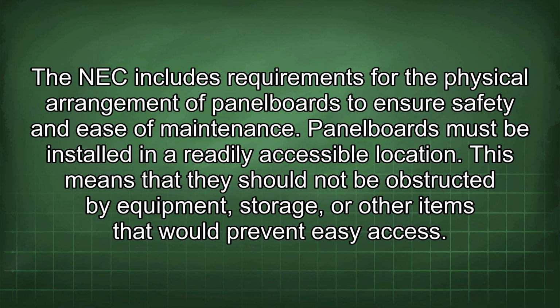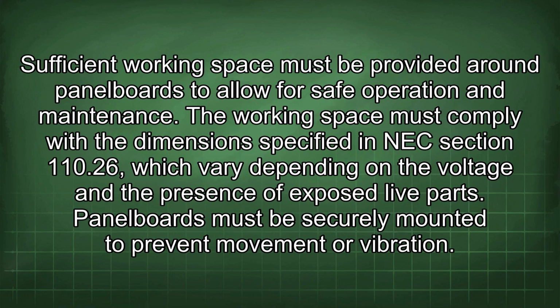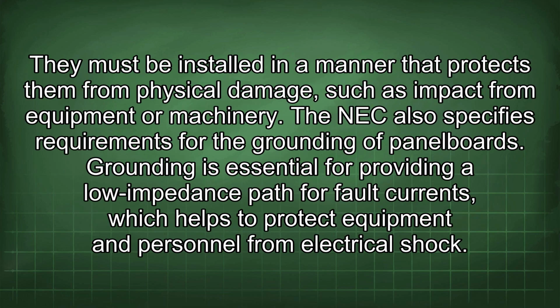The NEC includes requirements for the physical arrangement of panel boards to ensure safety and ease of maintenance. Panel boards must be installed in a readily accessible location. This means that they should not be obstructed by equipment, storage, or other items that would prevent easy access. Sufficient working space must be provided around panel boards to allow for safe operation and maintenance. The working space must comply with the dimensions specified in NEC Section 110.26, which vary depending on the voltage and the presence of exposed live parts. Panel boards must be securely mounted to prevent movement or vibration. They must be installed in a manner that protects them from physical damage such as impact from equipment or machinery.